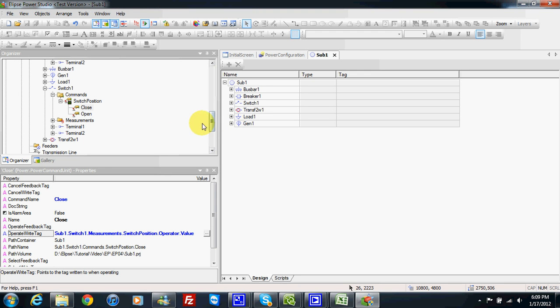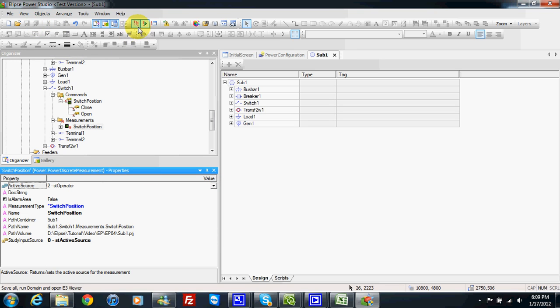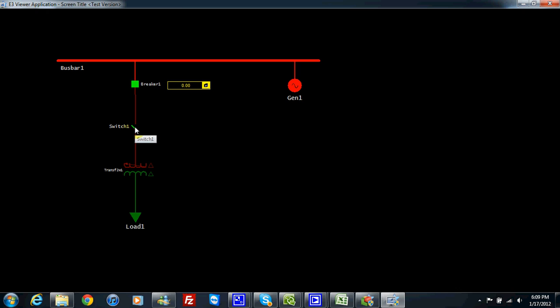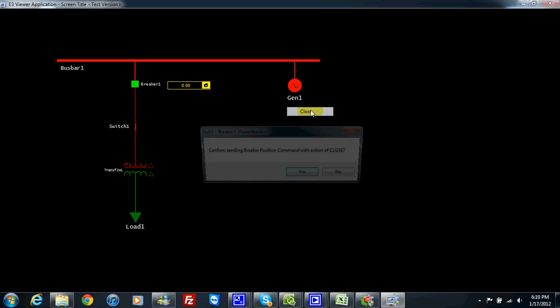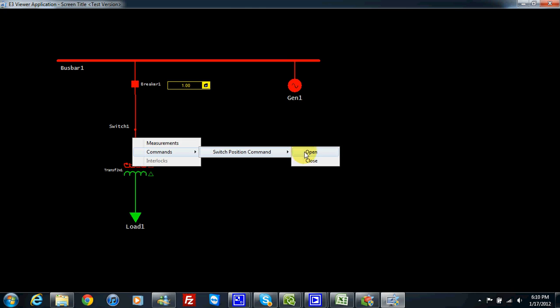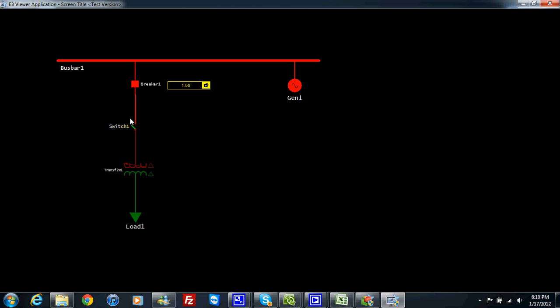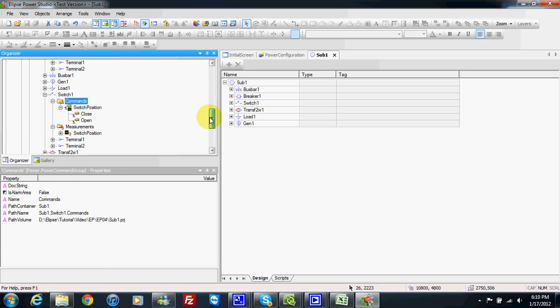I also need to remember that in my measurement switch position, by default the active source is SCADA, but I can choose operator. When I run, the switch is open, and then I can choose to close. Both terminals are not energized because the current is stopped by breaker one, so I close breaker one and the current goes through. Then if I open the switch, terminal one is energized and terminal two is not energized. This is how we can add a command to our system equipment.